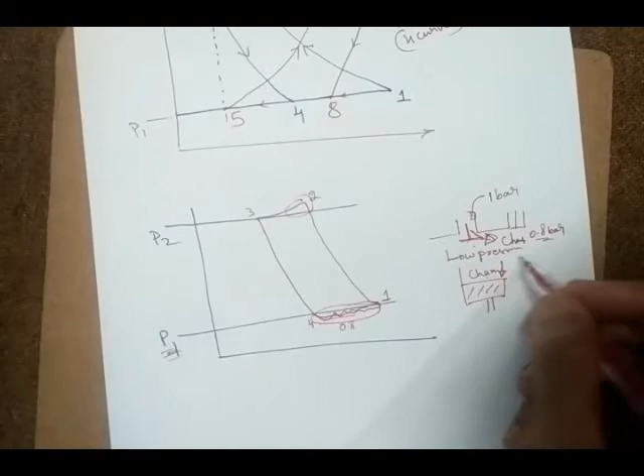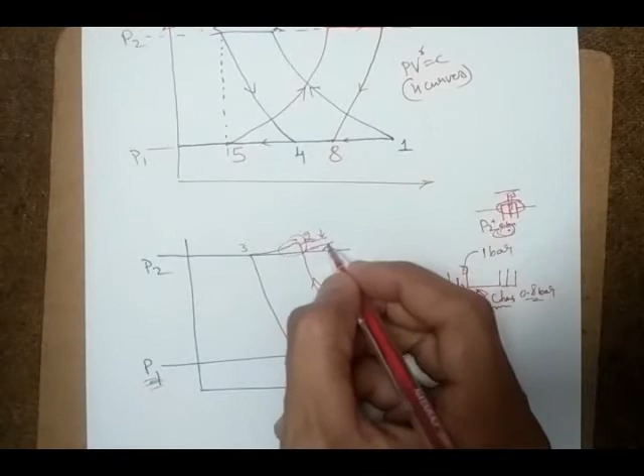this valve will be still closing the seat. So at P2, exactly at P2, the valve need not open. That's why we need to add a little more pressure, P2 plus say 0.1 bar. So the valve will get opened, so it will rise up. The extra pressure we have given will gradually come down back to P2. So it will come back to P2, which is the tank pressure.